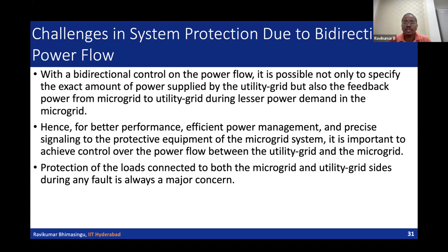For better performance and efficient power management, precise signaling to the power equipment is very important to achieve control over the power flow between the utility grid and the microgrid. And also, protection of the loads that are connected to both the microgrid as well as the utility grid during a fault is always a major concern.